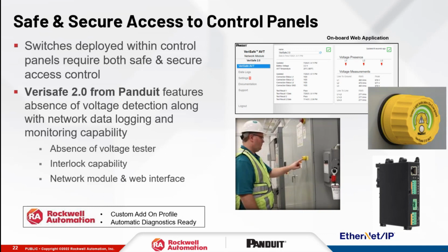The device is, in effect, a tester permanently installed to the power leads in the enclosure with a low voltage connection through the door. When activated, it tests whether it's installed and operating correctly, tests for phase connections and lack of voltage, and then provides a green signal saying it's safe to open the door in terms of arc flash safety.